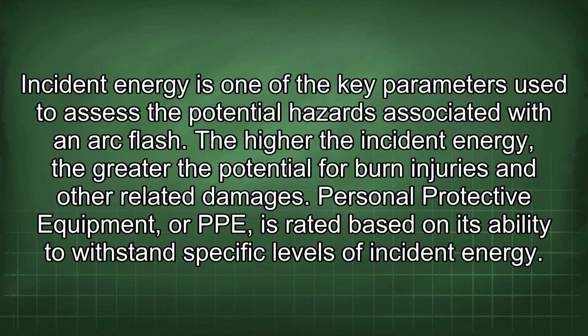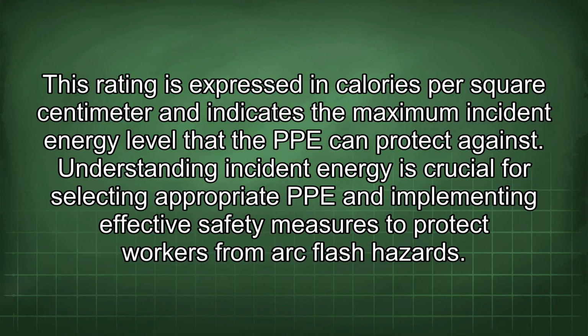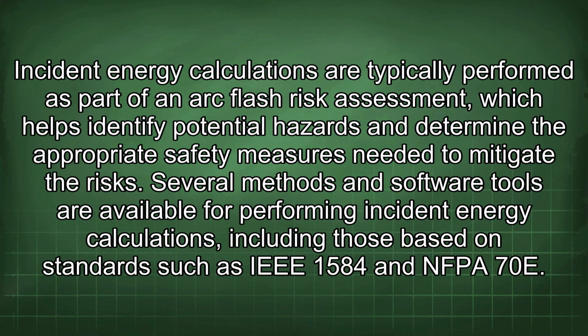Personal protective equipment, or PPE, is rated based on its ability to withstand specific levels of incident energy. This rating is expressed in calories per square centimeter and indicates the maximum incident energy level that the PPE can protect against. Understanding incident energy is crucial for selecting appropriate PPE and implementing effective safety measures to protect workers from arc flash hazards. Incident energy calculations are typically performed as part of an arc flash risk assessment, which helps identify potential hazards and determine the appropriate safety measures needed to mitigate the risks.